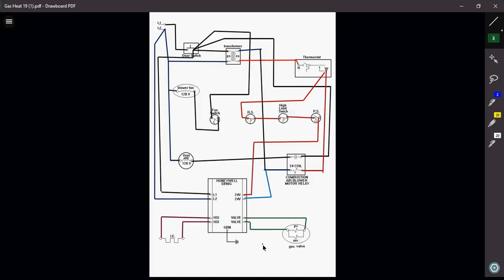the sequence of operation of a hot surface ignition system is very, very similar to a spark ignition system. The only difference out of the entire thing is your ignition source, whether it's a spark or a silicon carbide hot surface ignition system. So really, the sequence of operation for this unit is, once the thermostat calls for heat, I'm going to energize my relay coil, which will now energize my vent motor, which will start to spin to clear out any sort of combustible gases that may still be inside the heat exchanger.